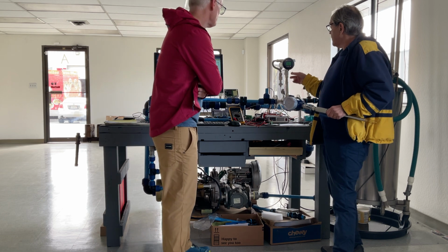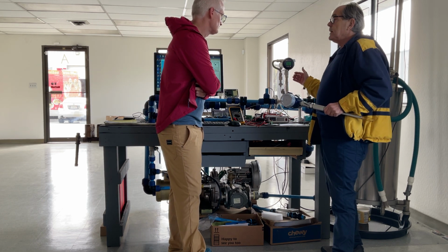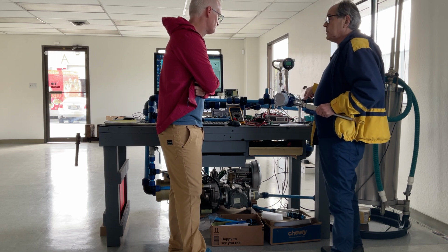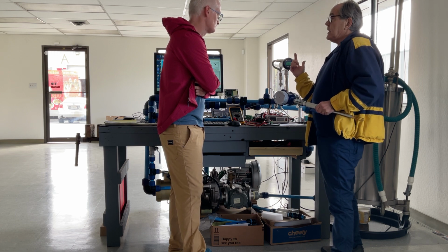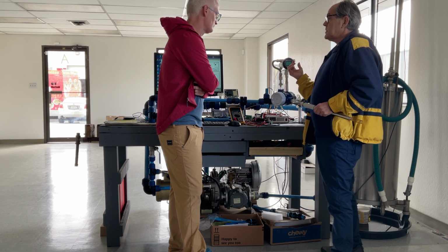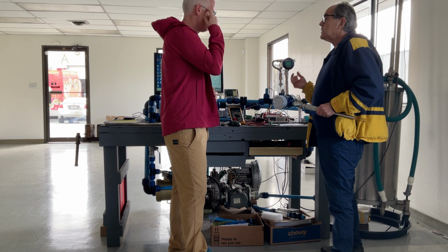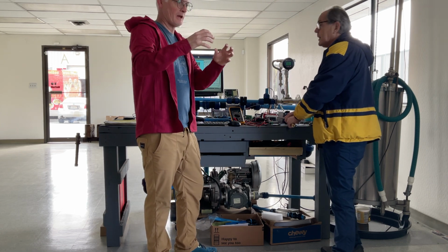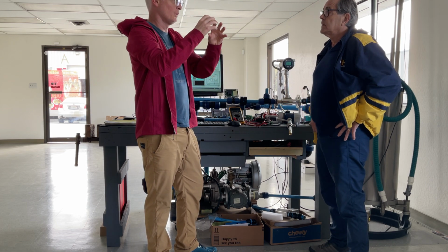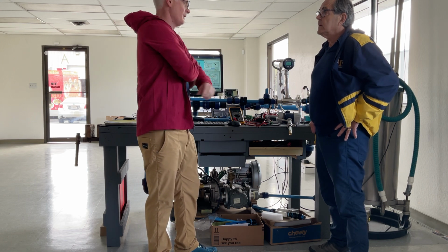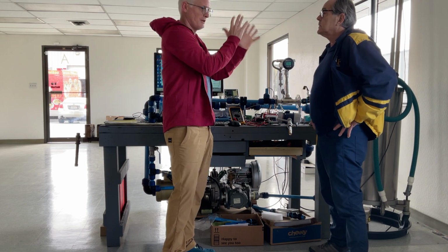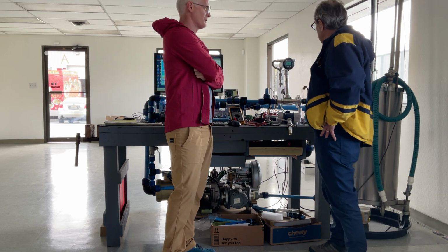This one, as a vortex meter, is a time domain machine. There's a bluff body in front of the flow meter. Behind it is a little piezo transducer. There could be many different methods of measuring the vortex shedding frequency. So maybe let's talk about a vortex. Essentially, if you have a river and you have a rock in the river, you're going to have this crazy stuff happening behind it. Or think about an airplane wing in a wind tunnel, you have this crazy stuff. So that's what we're measuring here: we have something blocking the flow, and it's creating all these vortices, and we have a piezo crystal measuring that vortex.